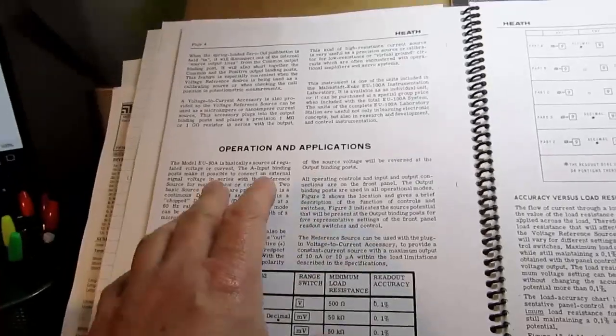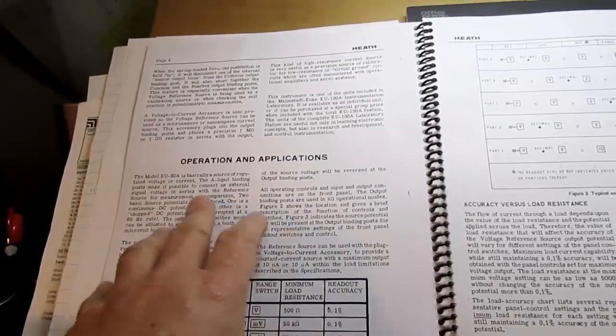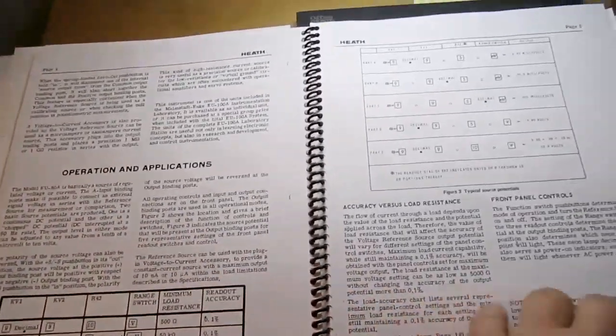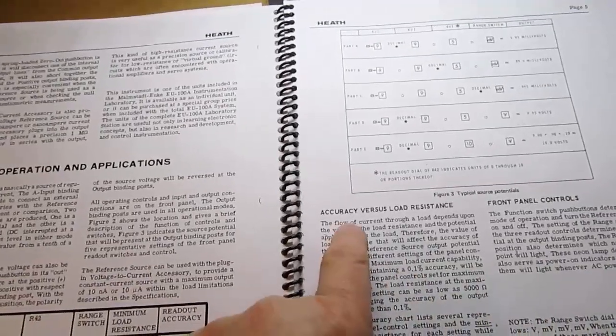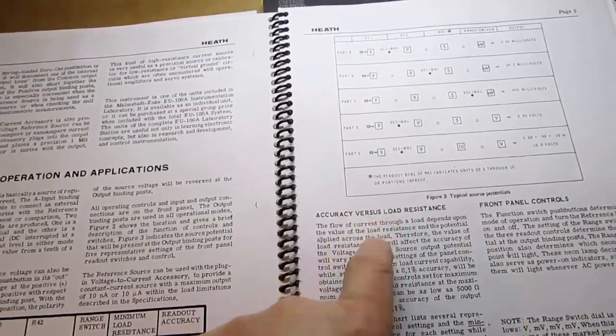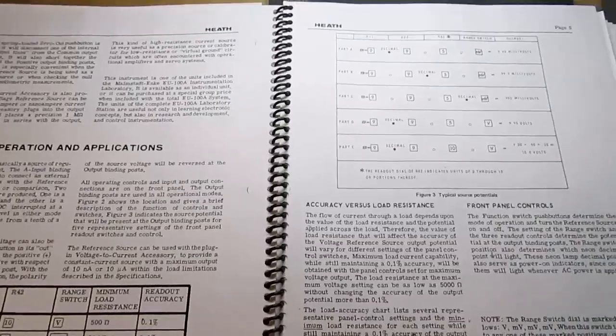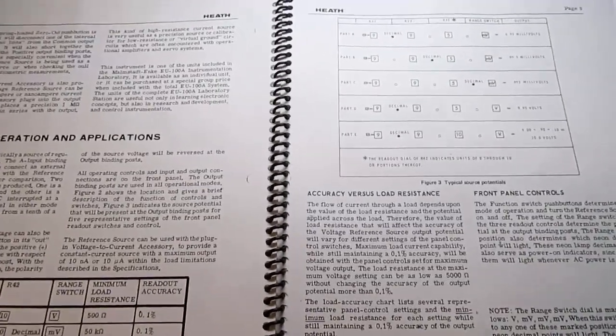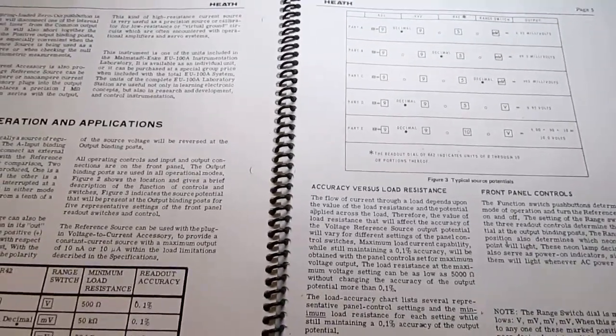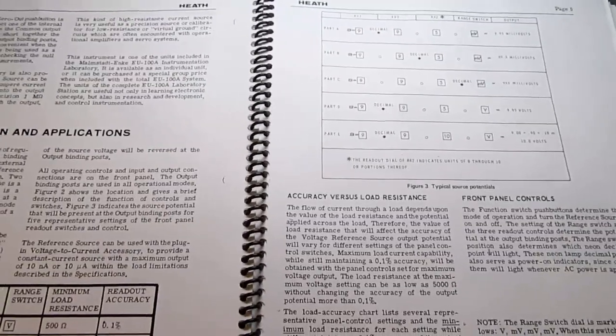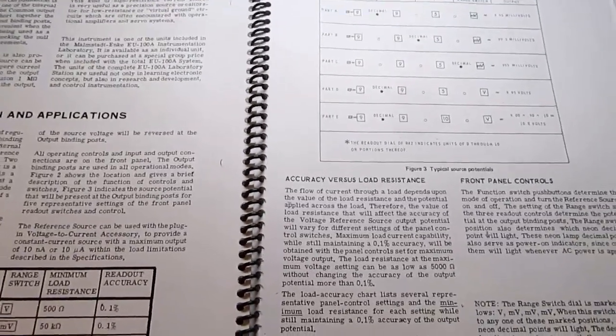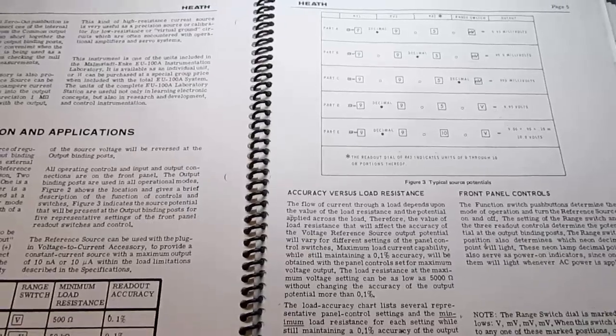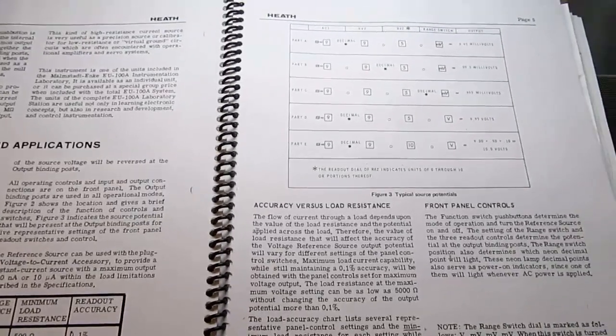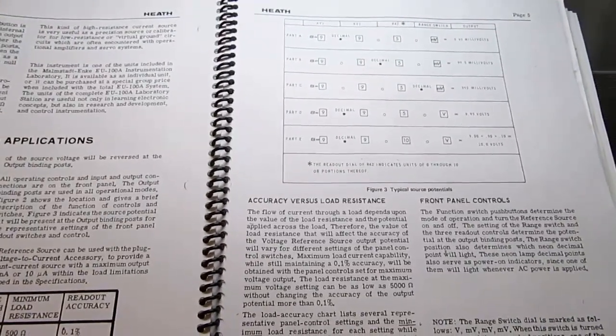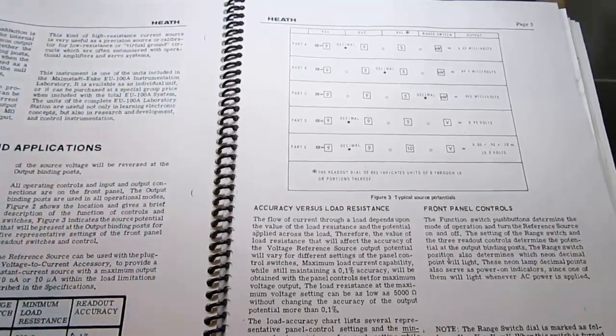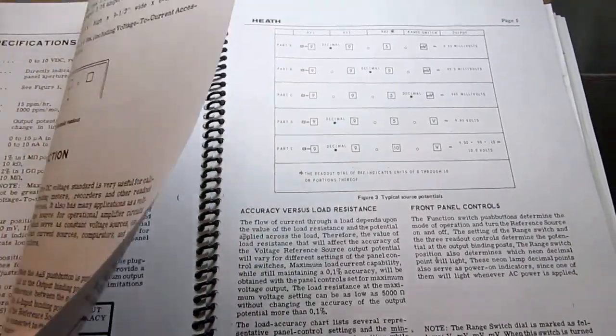Then we get into the operation part of the manual, telling you how to use it. It talks about accuracy and the impact of load resistance. You are not supposed to have a very low load resistance on this. It's not really a power supply. It's very limited in its ability to provide current output, so it really should go into high input impedance circuits.